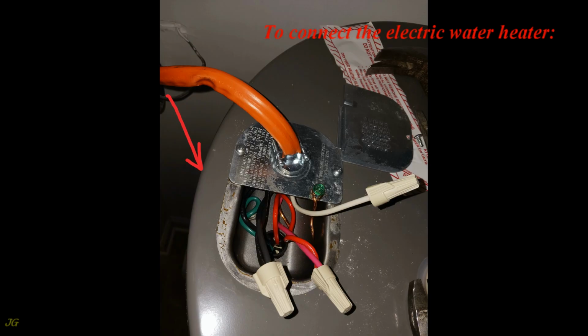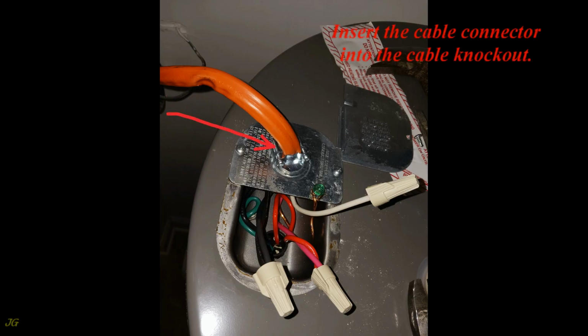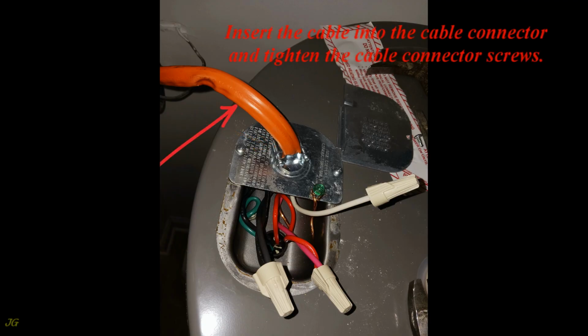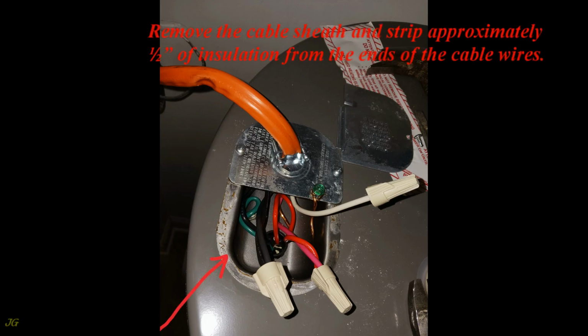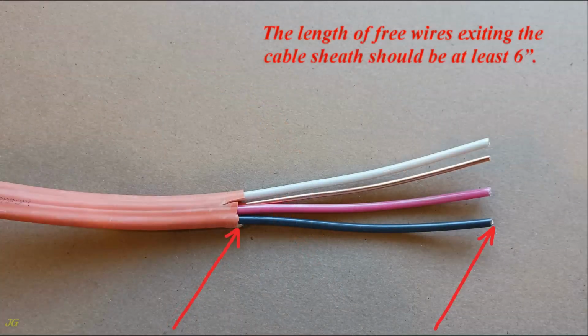To connect the electric water heater, insert the cable connector into the cable knockout. Insert the cable into the cable connector and tighten the cable connector screws. Remove the cable sheath and strip approximately 1/2 inch of insulation from the ends of the cable wires. The length of free wires exiting the cable sheath should be at least 6 inches.